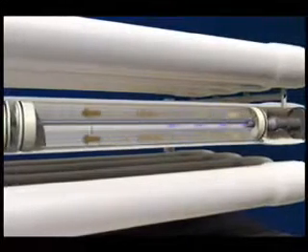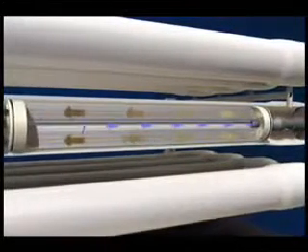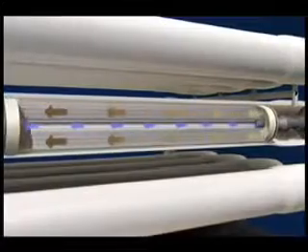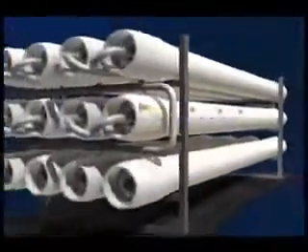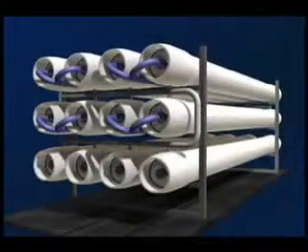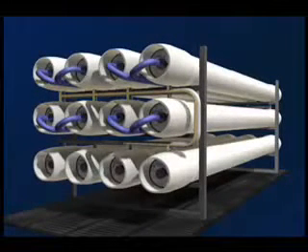The feed water that does not permeate through the membrane becomes enriched in salts as it travels through the feed channel spacer due to permeate water being removed. Typically, 8-10% of the water is removed in one 40-inch-long membrane element.